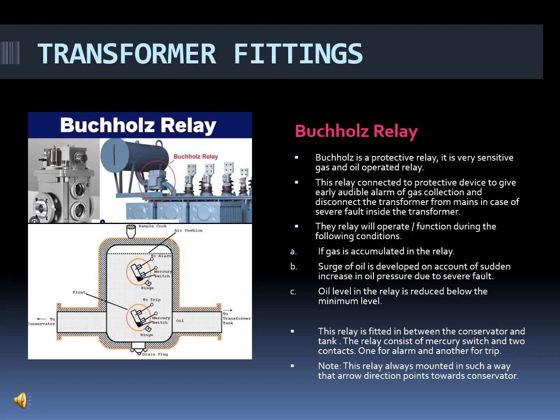The relay, we will understand when the relay will operate or function. The relay will operate during the following conditions. If any gas is accumulated inside the relay, then the relay will operate. If a surge of oil is developed on account of a sudden increase of pressure inside the transformer due to a severe or sudden fault, then the relay will operate. Or if the oil level in the relay is reduced below the minimum level, at that time this relay will operate.